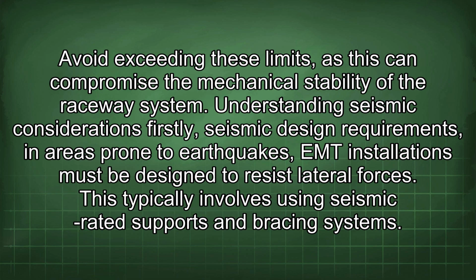Avoid exceeding these limits, as this can compromise the mechanical stability of the raceway system. Understanding seismic considerations. Firstly, seismic design requirements. In areas prone to earthquakes, EMT installations must be designed to resist lateral forces. This typically involves using seismic-rated supports and bracing systems.